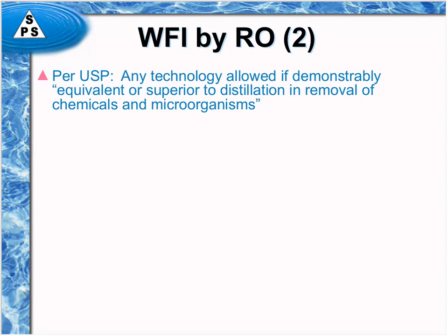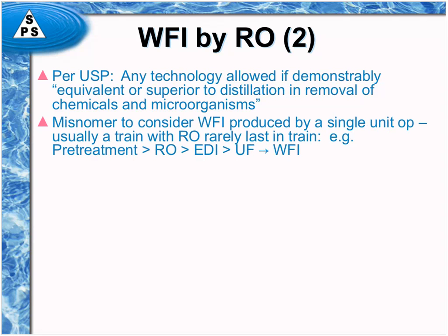Those are words that were actually requested by FDA to be placed in lieu of what USP's opinion was, which was that any technology can be used as long as it's validatable, and that's the essence of it. But we acquiesced and said, okay, you just have to demonstrate that it's at least as good as distillation for the removal of chemicals and microorganisms.